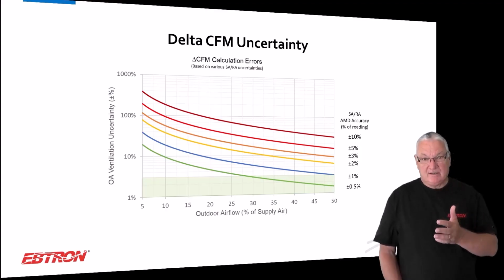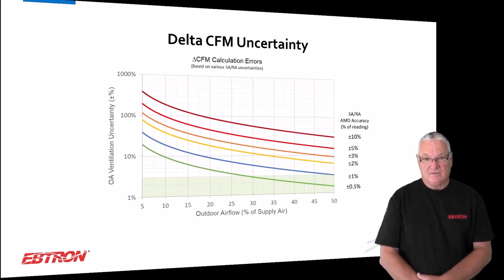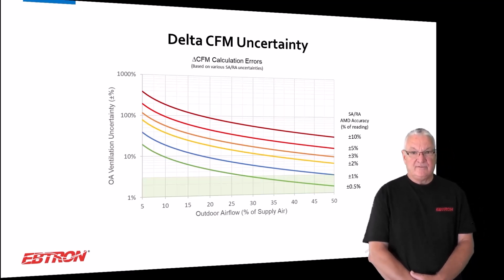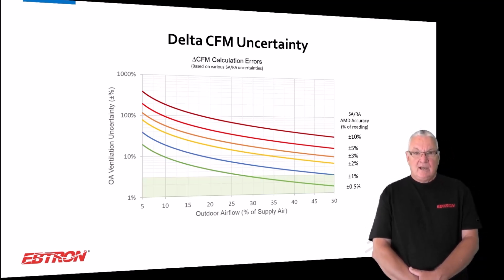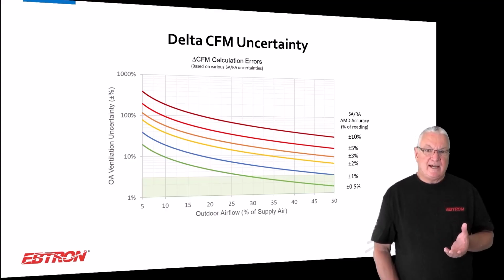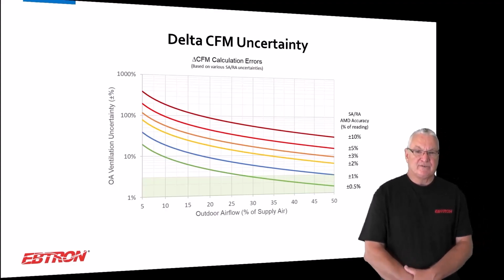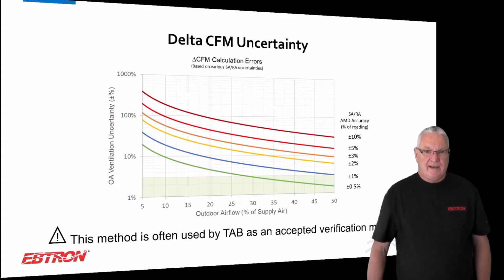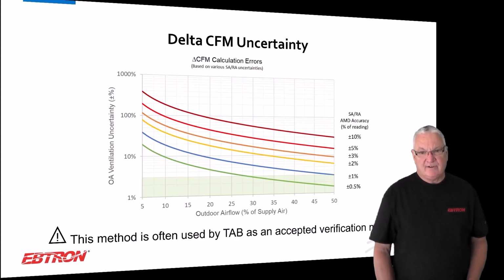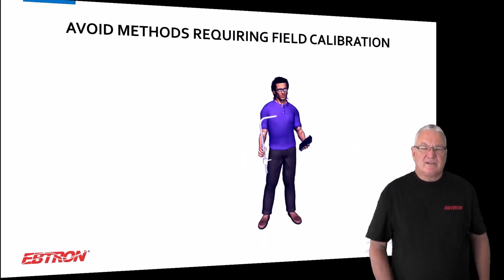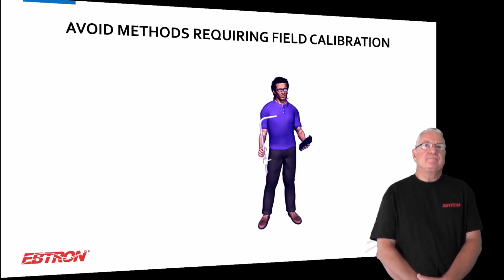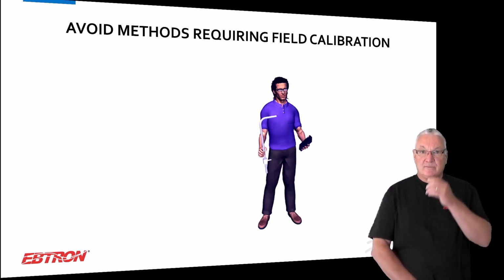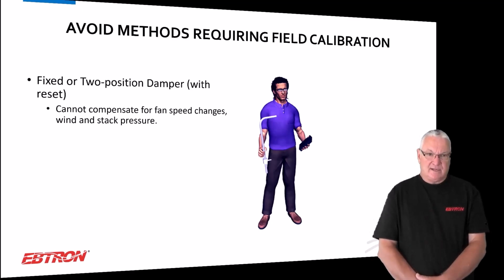So make sure you understand that the different curves there are different uncertainties of the supply and the return flow measurement, because you're measuring a differential. So the inaccuracy of the differential is much larger than the inaccuracy of the device you're measuring it with. And again, this method is often used as a verification method. Now you might say, okay, I guess I shouldn't use those two methods. I'm going to do something else. So what is the something else?